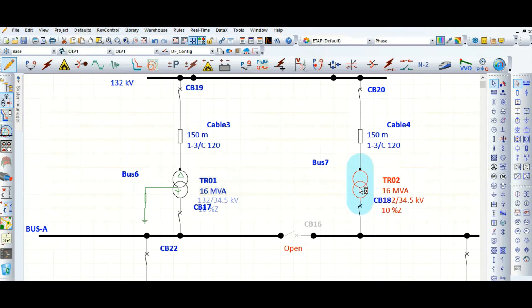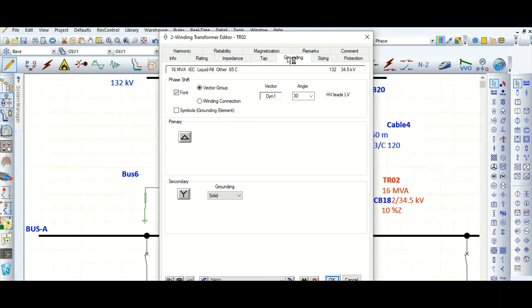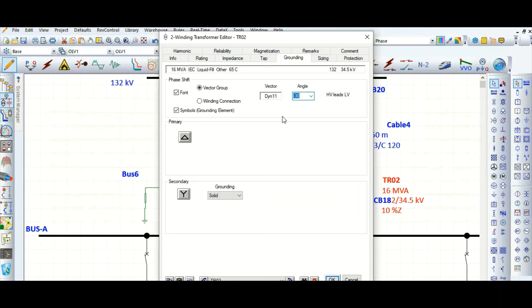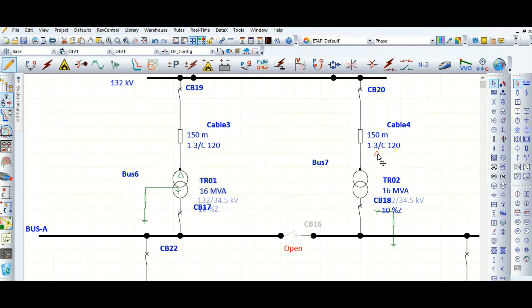Similarly, for this second transformer, go to the grounding tab and check the box. It is delta-star, but select angle minus 30 — that means dyn11. It is resistance grounded and will restrict to 300 amps; the ohm value will be calculated automatically.